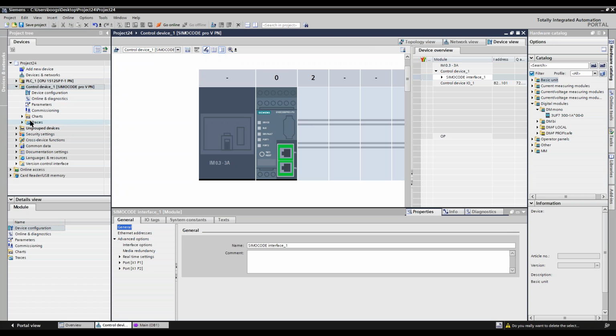Okay, so now that it is set up in my system, I want to talk further about the device setup itself. When I told it that it was going to be a reversing pumping application, it put in the hardware config of just exactly what I needed. I gave it the full load amps, so it put in current transducer only for 0.3 to 3 amps, because that's within the specifications of my full load amps of my motor, and it gave me a basic unit. That's it. That's all it gave me.